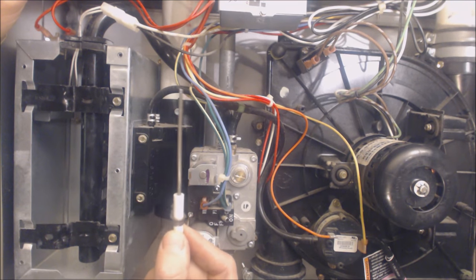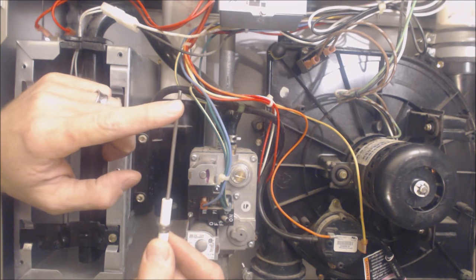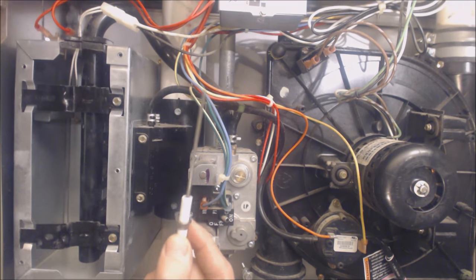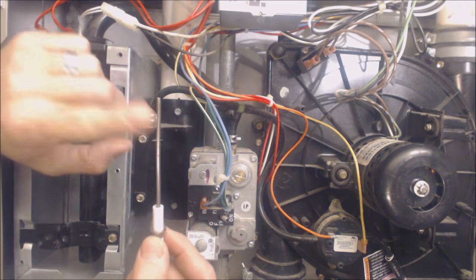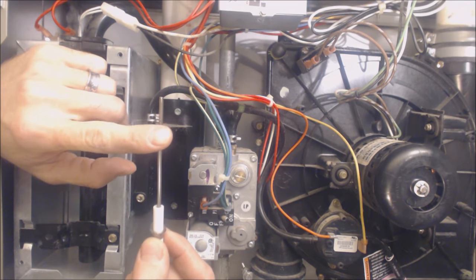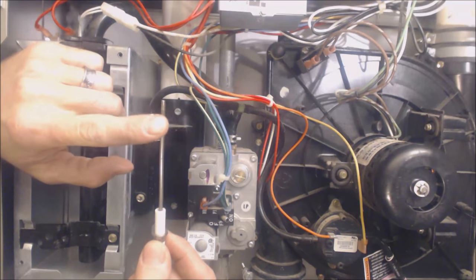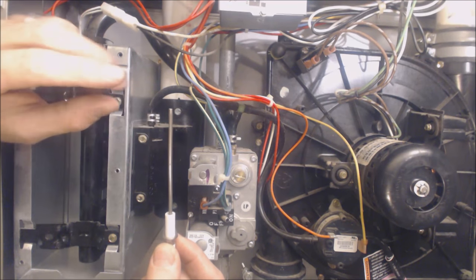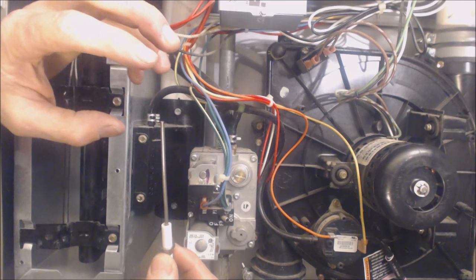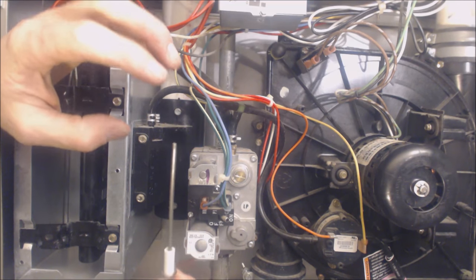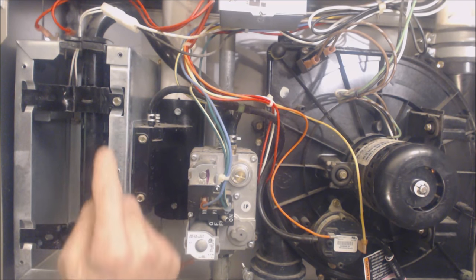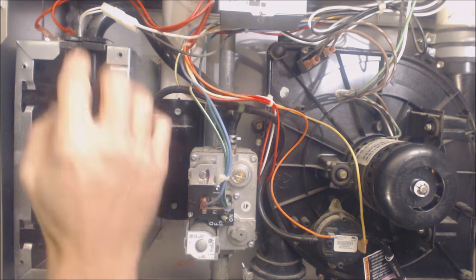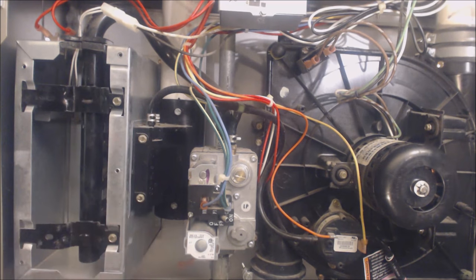When you do that, when you put 90 to 110 volts into the flame, the actual voltage rectifies. And it's going to go towards the larger surface area, which in this case is going to be the burner retention head inside this box right here.